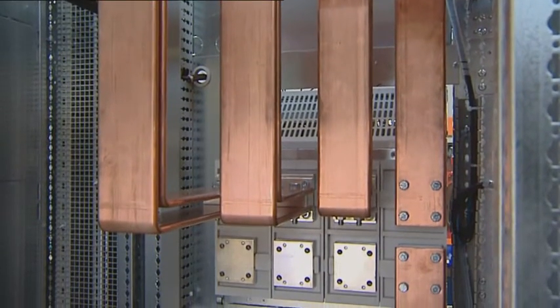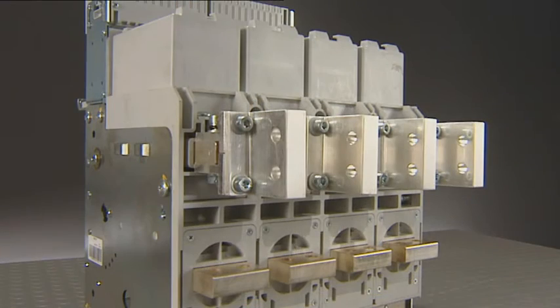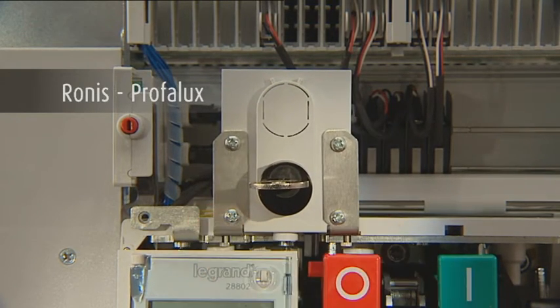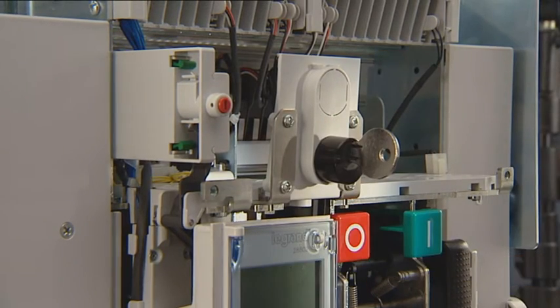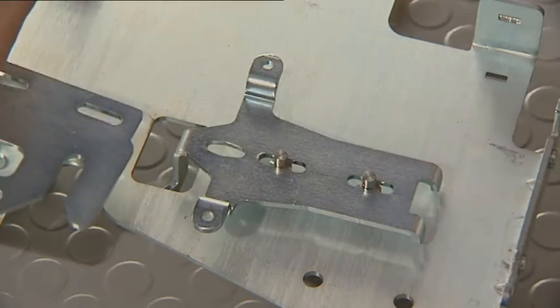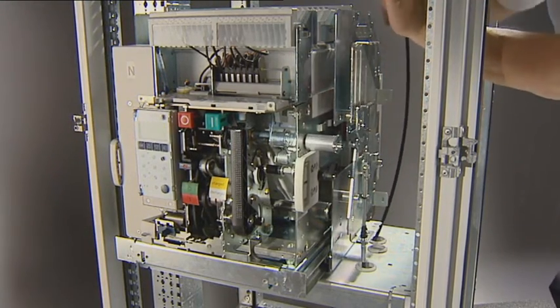The full range of terminals allows connecting the circuit breakers in various flexible configurations. Maximum attention has also been given to the safety and padlocking accessories, that offer installers an increased security. Mechanical interlocking can be easily achieved between two or more switches, using a kit consisting of a plate according to the size of the breaker and a cable of various lengths.